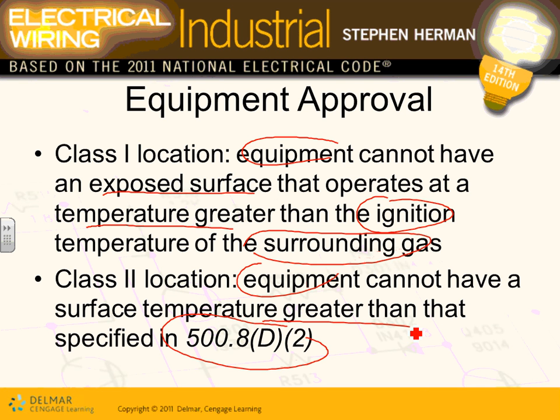Explosion proof equipment has two functions. Number one, it doesn't allow the gas to get into it. Okay. And if it got into it and there's an explosion inside it, it doesn't spread the explosion outside. It doesn't get the gas and ignite the whole area. And at the same time, the temperature around the explosion proof box does not get hot enough to ignite the surrounding as well.